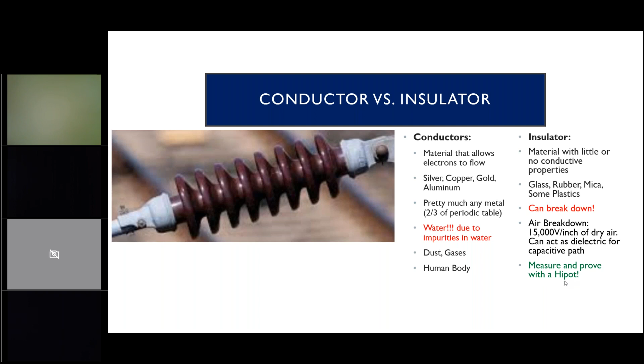Same thing for air. At 15,000 volts per inch in dry air, it'll arc over and break down, and you'll have a big spark gap going on. So the nice thing is, if you have a HIPOT, you can measure if it's a conductor or an insulator, and you can prove it.